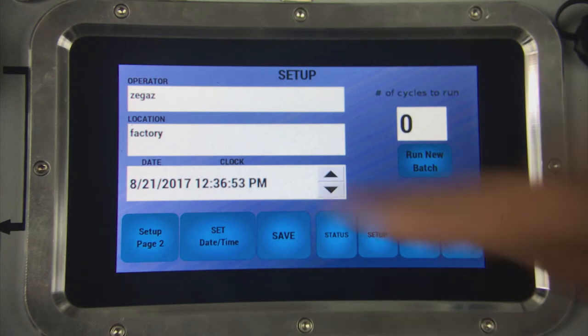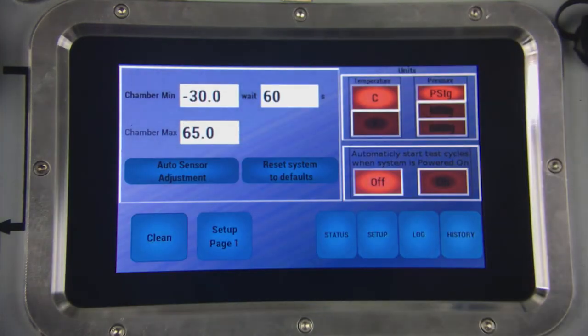On page two is where you can select your units for temperature in Fahrenheit and Celsius and pressure: PSI, bar, and kilopascal. You can also set a higher minimum temperature if you don't require the unit to cool down to the minus 30 Celsius limit to detect a dew point. You may also set a longer wait time between cycles.